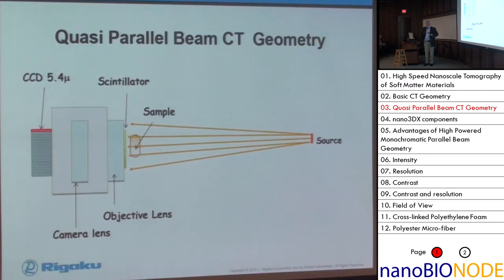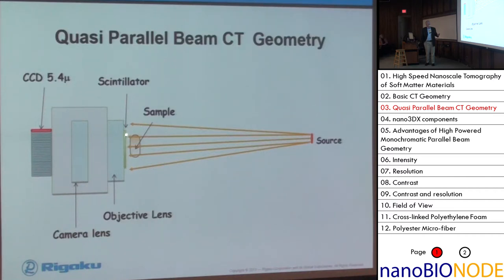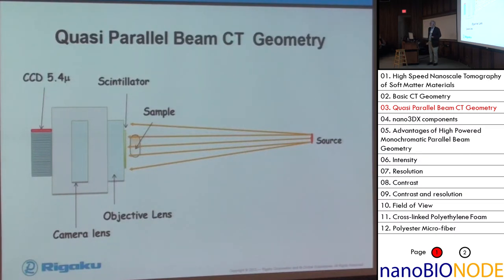So what we've developed at Rigaku is what we call a quasi-parallel beam CT geometry. One of the things it allows, starting from the source side, is to use a much larger source. The reason for that is the resolution is actually not coming from this x-ray source - it's coming from the scintillation effect that happens at the YAG scintillator. Because this source can now be larger, we can move the sample further away from the source, since we're not going to be looking for magnification from the x-rays. Because of that and the larger size, we can get a larger field of view than we would typically see on a traditional CT.